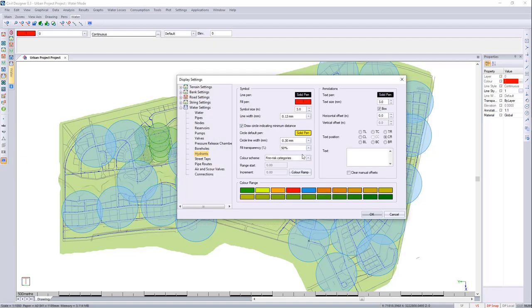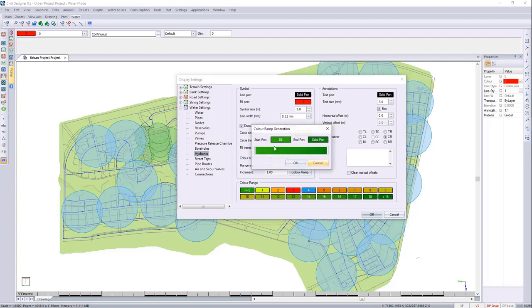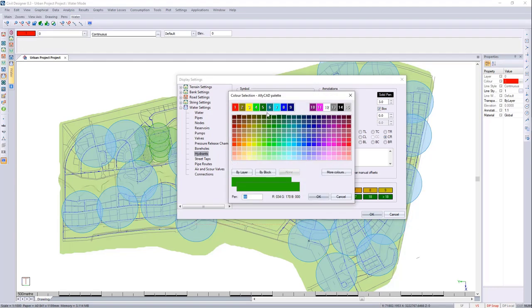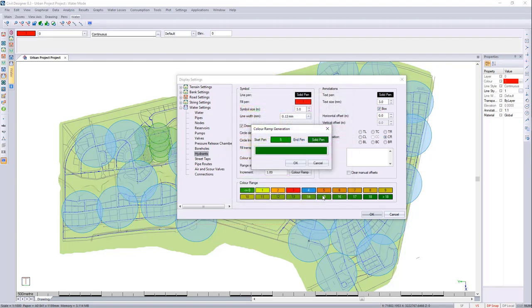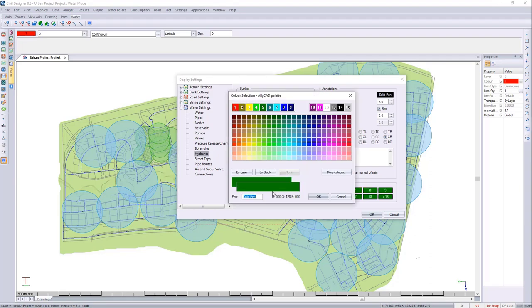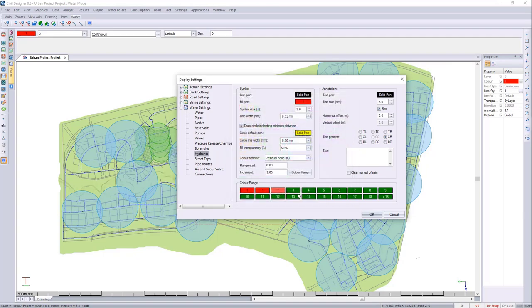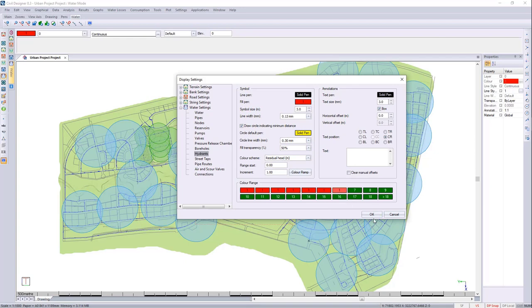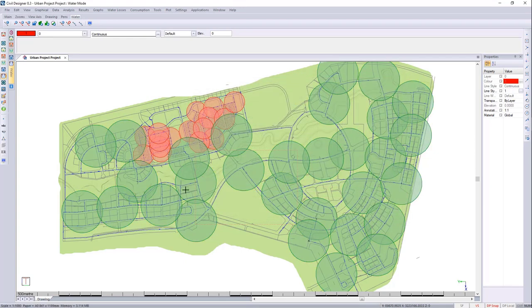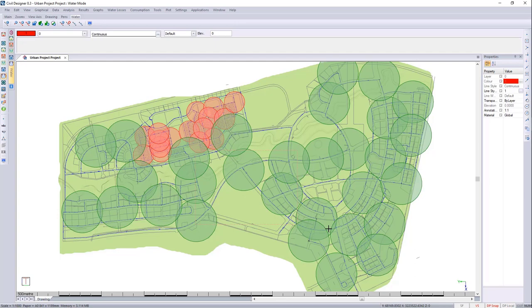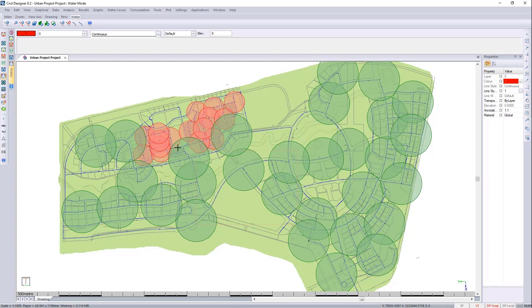Let's change this to the residual head. Now remember it was 7 for the low risk. Here you can see that during the analysis, these ones are having a pressure issue with lower than 7 where these are coping just fine. But remember that these ones are running with no others open during the radius where these are open with others in the radius also open at the same time, resulting in a lower pressure. So you will need to bring up your pressures in this area as well to cater for the more hydrants open at the same time.